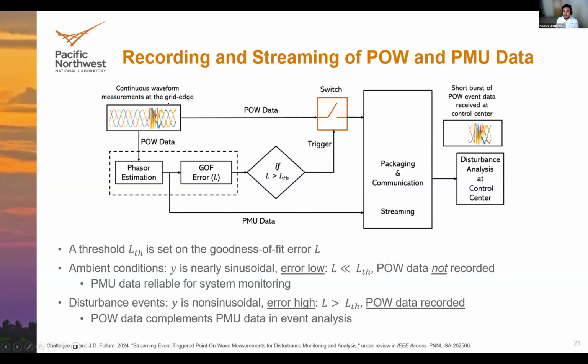So you have your continuous waveform measurements at the grid edge. You do phasor estimation on it. You get PMU data, but besides that, you're also getting this goodness of fit error. You compare that goodness of fit error with a threshold, which you have pre-decided or preset. If that error is high, it's an indication that your data is non-sinusoidal, and therefore PMU data might not be good enough by itself. So you need to complement it with something else.